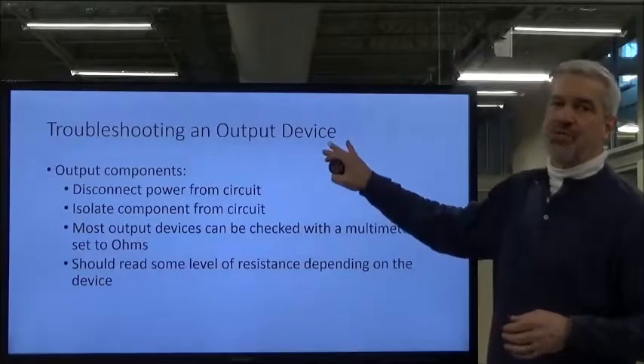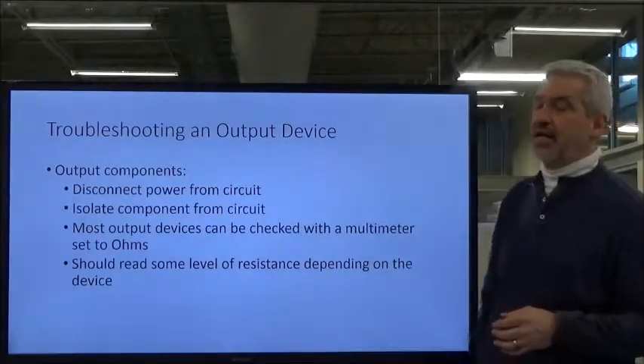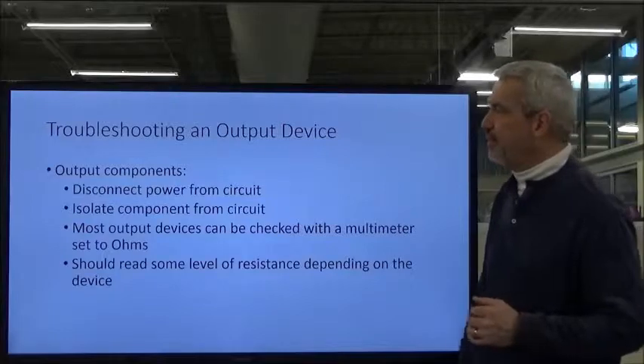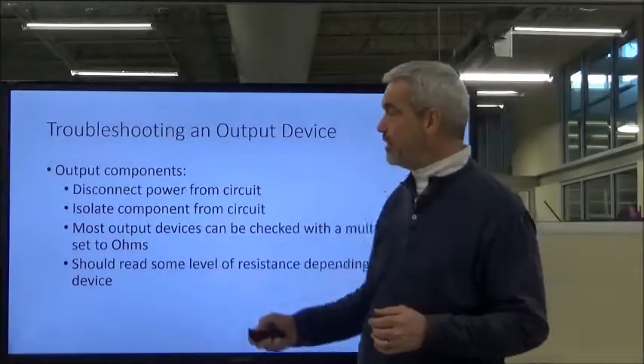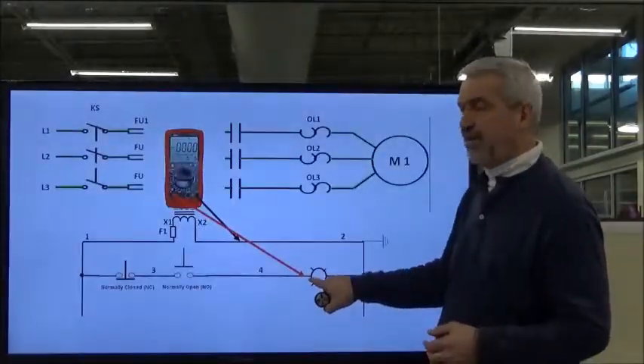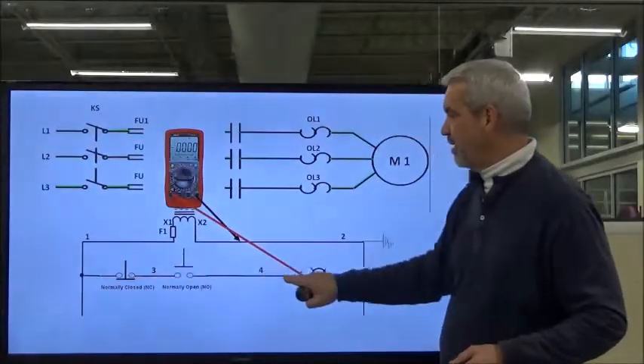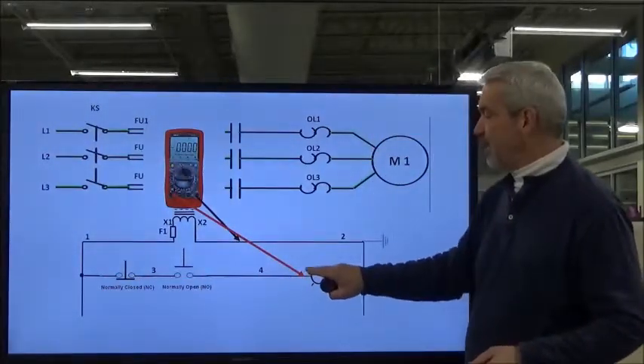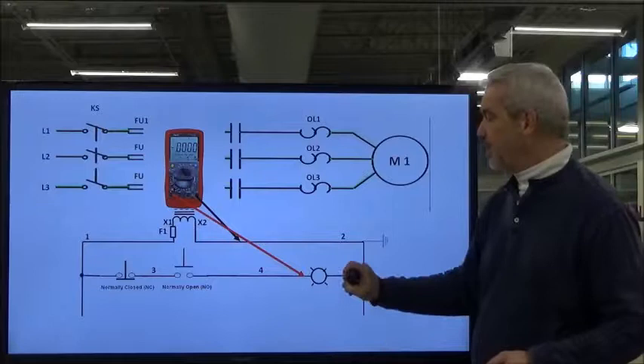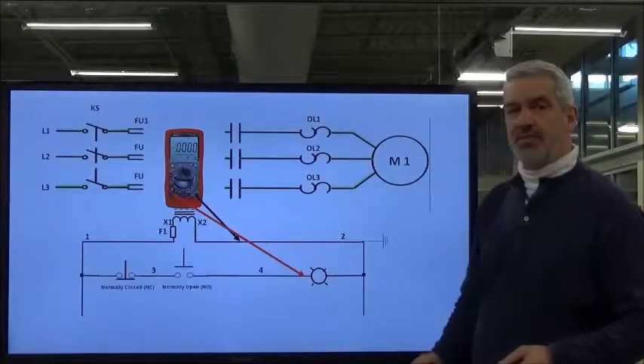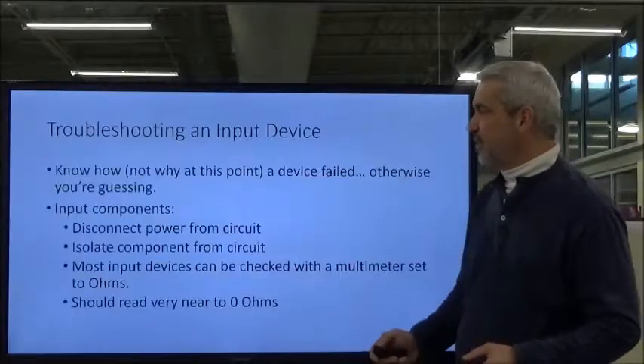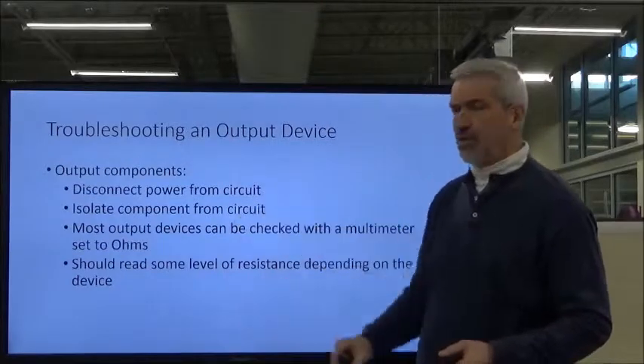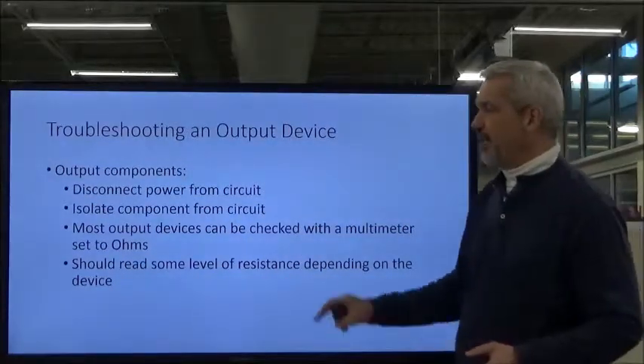Likewise with outputs, they're very similar to checking input devices, but a little bit different. We want to first make sure power is getting to our output device. Let's make sure the switches are actually delivering power before we decide it's bad. If power is right there, we want to start checking it. So how do we do that? We disconnect the power and isolate the component.